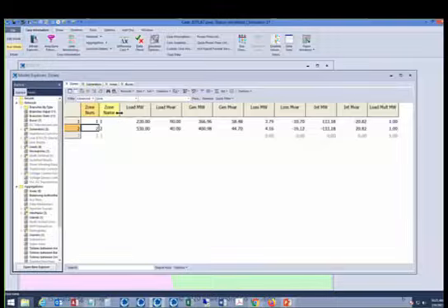Sometimes if I'm modeling an interconnected generator that doesn't exist yet, I like to drop it into its own area, and that way I can play around with the exports. I can export the power to area A or area B or whatever and see how that changes.